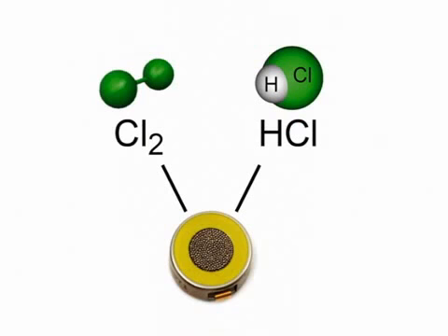Silicone vapors and chlorine and fluorine compounds, such as chlorinated hydrocarbons, can damage the % LEL sensor. These compounds should be avoided. If exposure to these compounds is suspected, verify the % LEL response on a known gas sample.